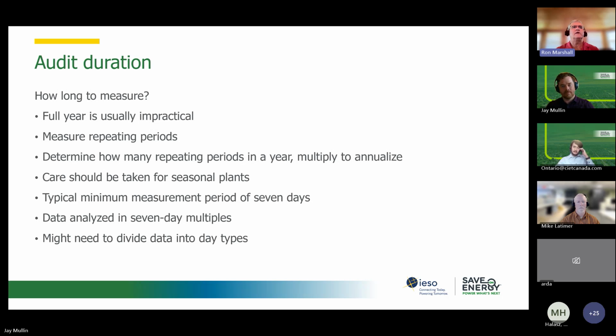When we measure, we'd like to do repeating periods. So very often it's a 1 week period, right? Monday, Tuesday, Wednesday, all the way to Sunday again, right? There'll be repeating periods, and we might do more than just 1 week, could be a month's worth of repeating periods. And we would determine the KPIs within those repeating periods, and then multiply by the number of hours that system might be operating, right? We need to take into account some food plants are seasonal, right? So if we take a reading during the high season, it may not equate to a full annualized cost if there's quite significant time in a light loading condition, right? So we have to make sure that that's accounted for.